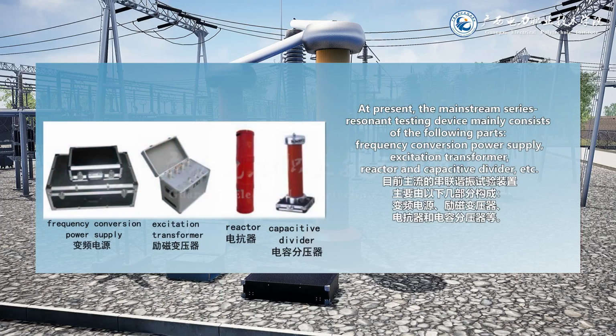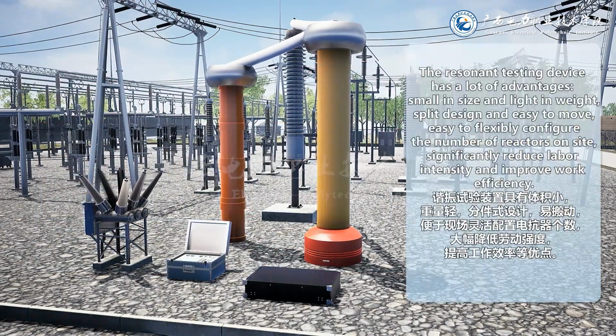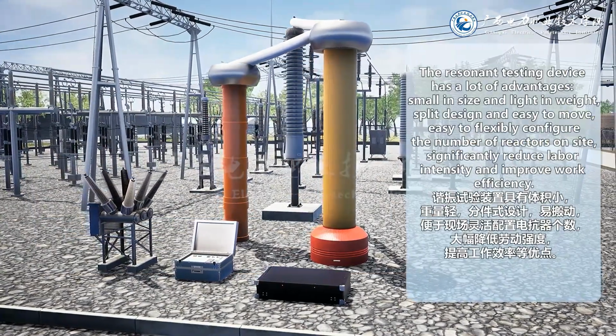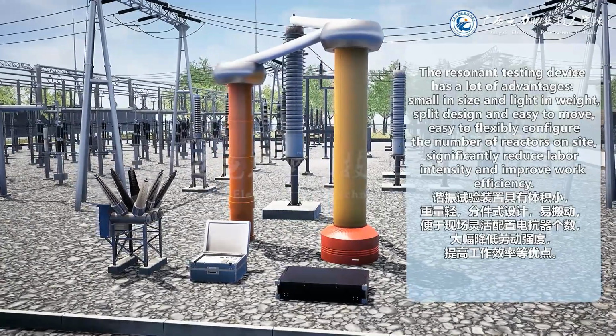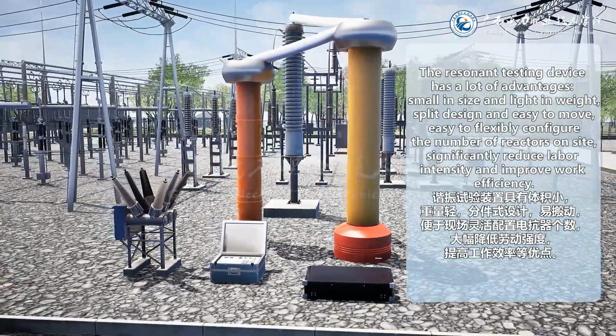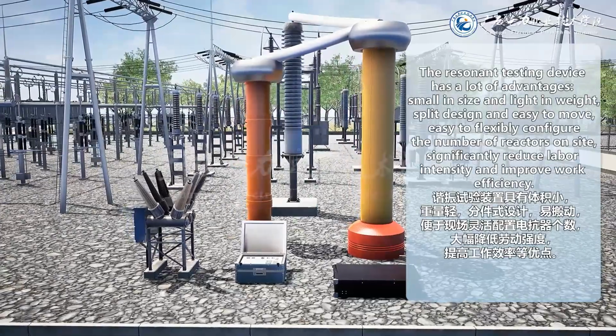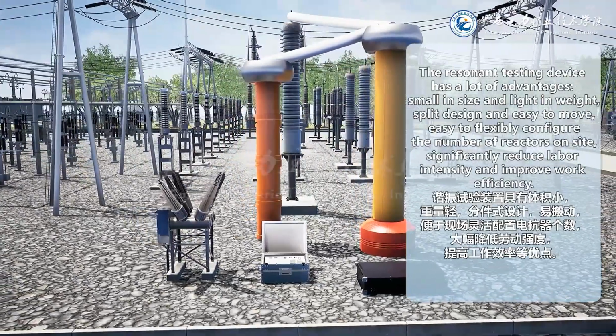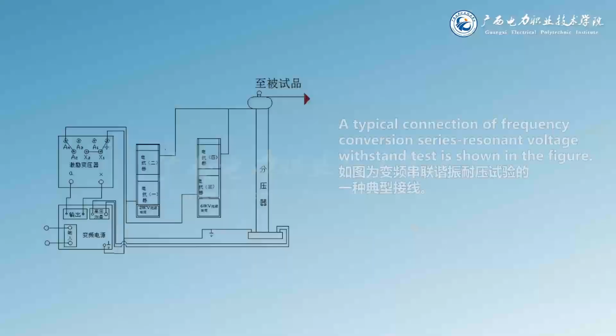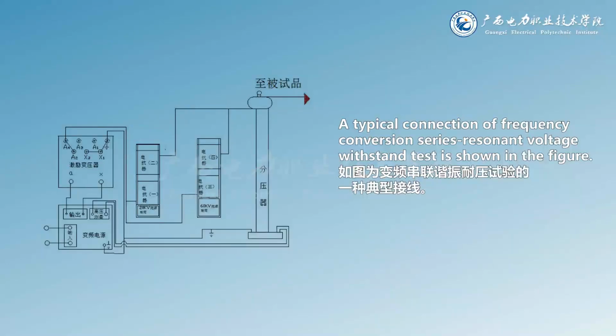At present, the mainstream series resonant testing device mainly consists of the following parts: frequency conversion power supply, excitation transformer, reactor and capacitive divider, etc. The resonant testing device has a lot of advantages: small in size and light in weight, split design, and easy to move, easy to flexibly configure the number of reactors on site, significantly reducing labor intensity and improving work efficiency. A typical connection of frequency conversion series resonant voltage withstand test is shown in the figure.